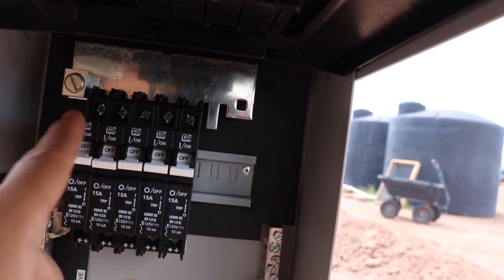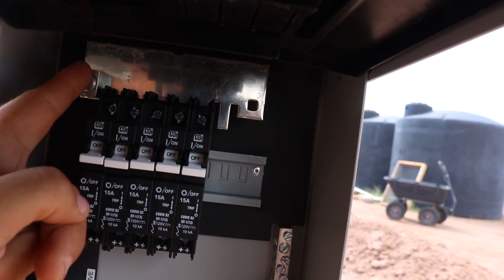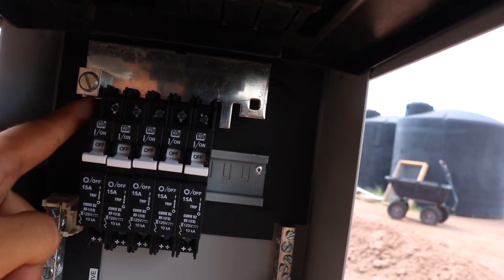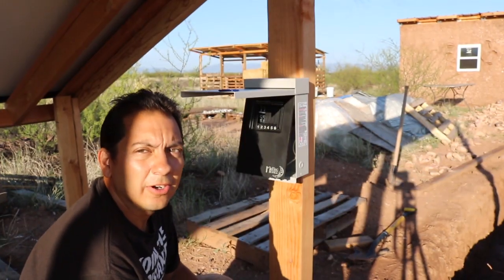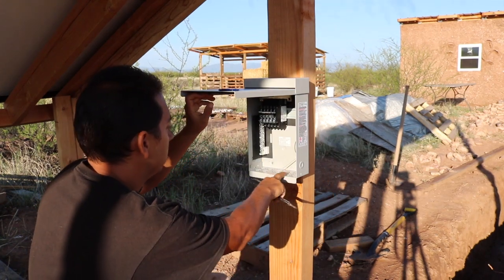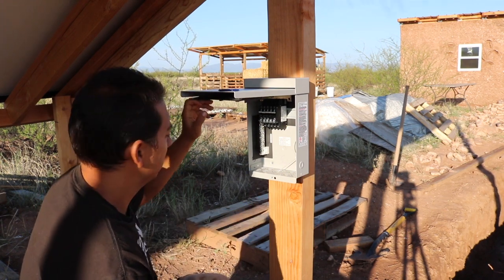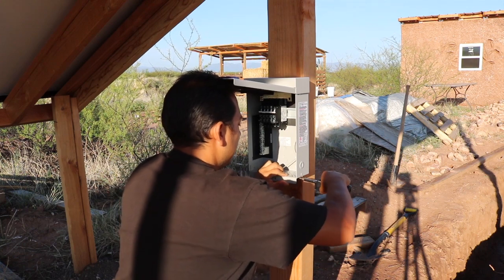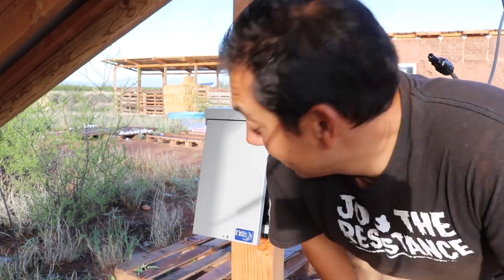Here's the finished product — I got my breakers in, they're attached to the bracket. This is now the positive bus bar, and this is where I'll attach the positive cable going out to the charge controller. Not too bad. To finish getting this combiner box ready I'm going to need to remove all of these knockouts because I'm going to be using them all. And that was pretty much it for getting the combiner box ready.